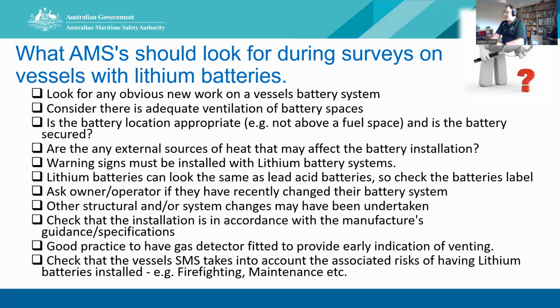Good practice is to have a gas detector fitted to provide early indication of venting. Studies have shown that when a lithium-ion battery gets close to spontaneous combustion, it releases trace elements of gases. So if you can monitor those prior to reaching it, there's a chance of actually throttling back and hopefully preventing it. But most of this is controlled by the BMS, so if the BMS is working, this shouldn't happen, but as we've seen, it can happen.